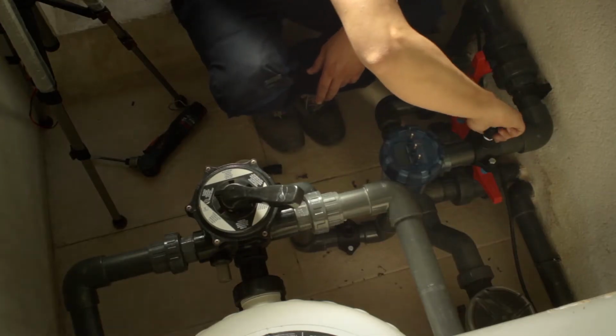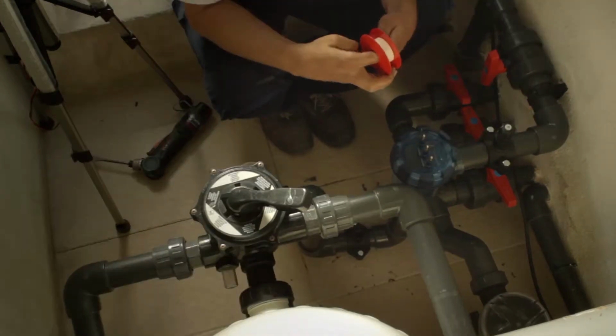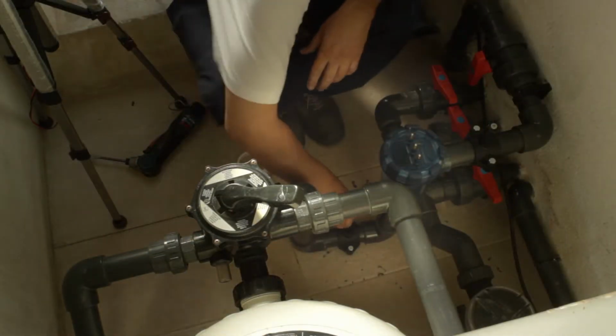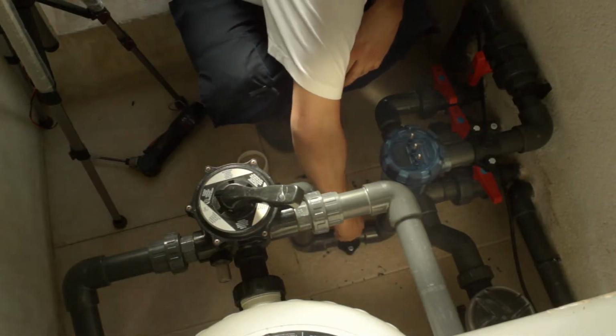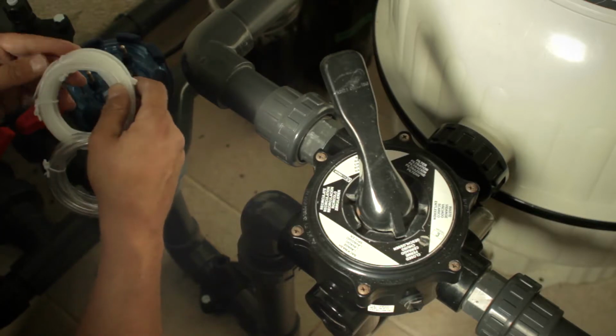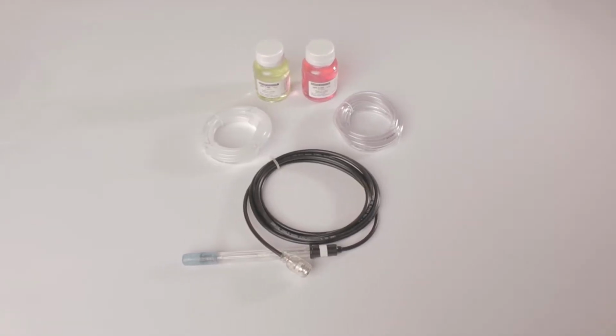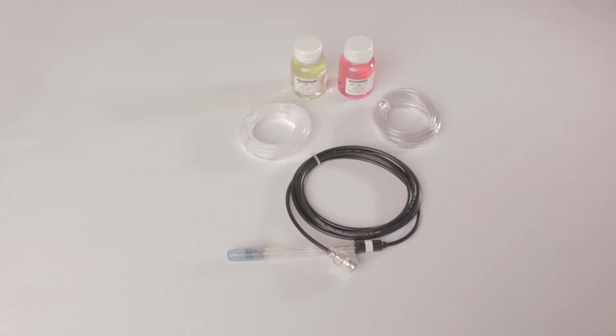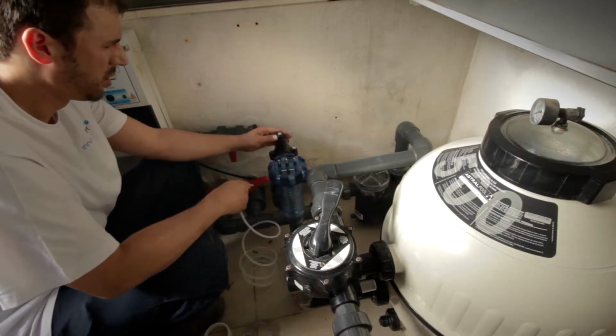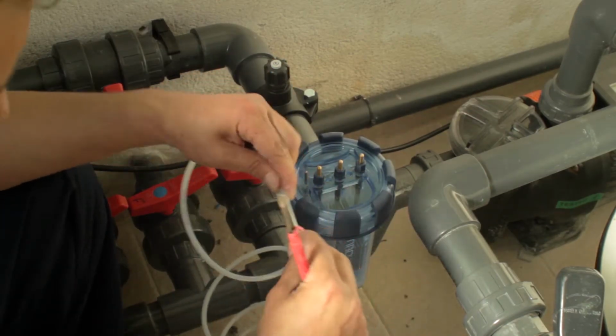Place the acid injector after the cell and the probe housing before it. There are two pipes. The stiffer opaque pipe will be used for the injection in case there are pressure problems. The softer pipe will be connected to the acid tank.